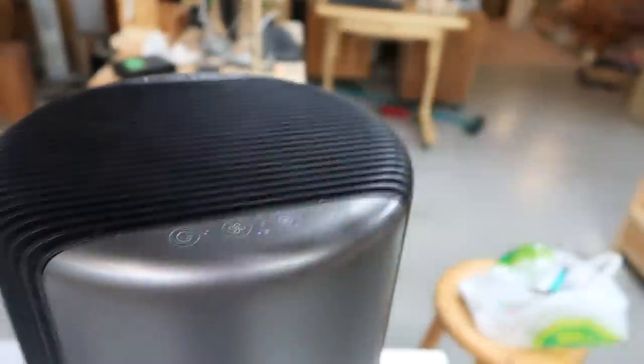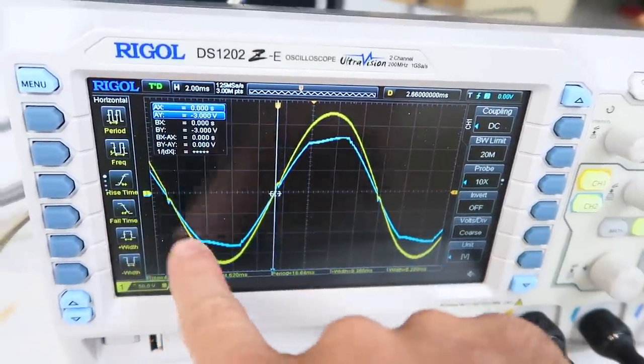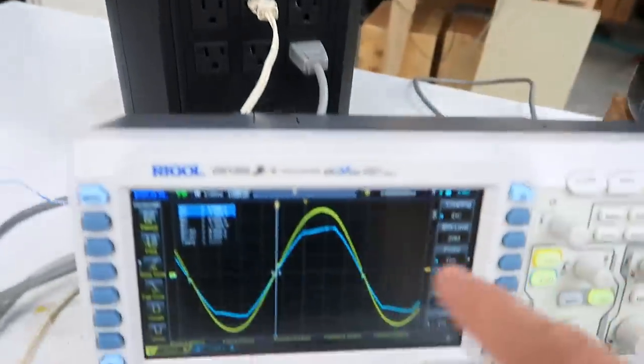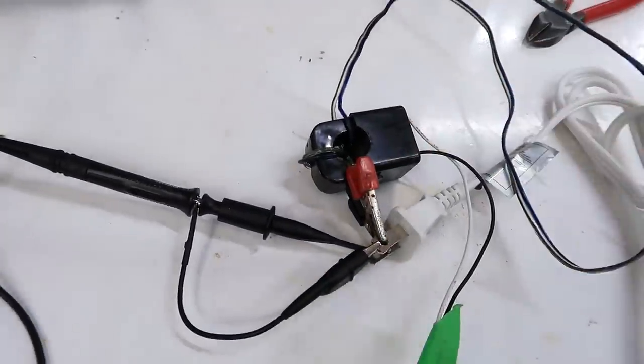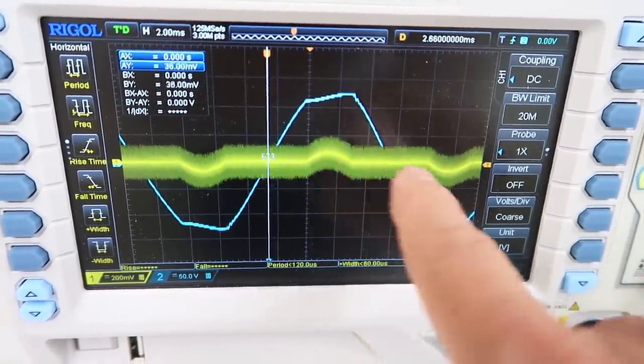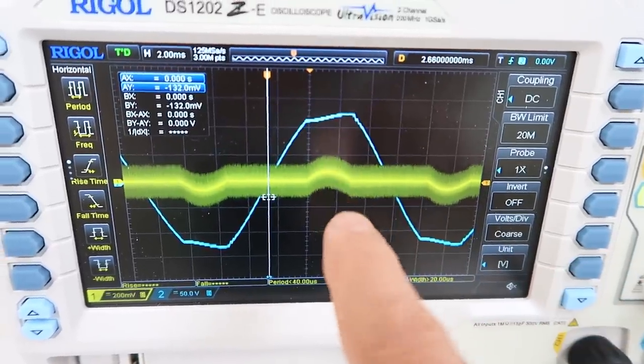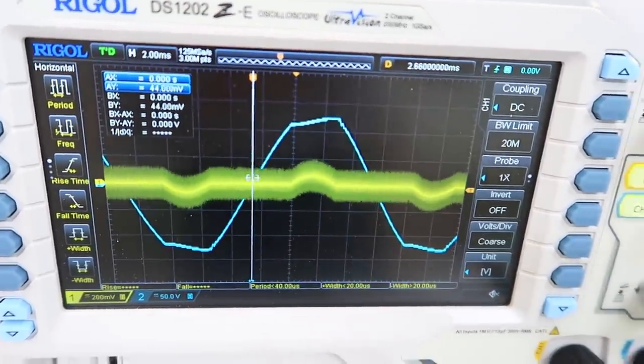Let's set it a bit higher. And now that flat spot is much more noticeable, even though the yellow waveform coming from the EcoFlow box is still a nice sine wave. And now using a current transformer to measure the current, which is now in yellow here, we can see a bump of the current always at the peak of the waveforms. So that current peak is causing the top of the waveform coming out of the transformer to be flattened. So it's the combination of transformers in the system and semiconductor devices with all willy-nilly current waveforms that cause our power to be all wobbly.